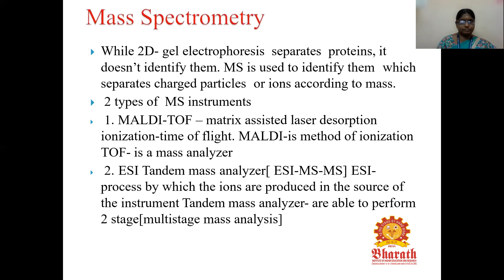There are two types of mass spectrometry instruments. The first one is MALDI-TOF, that is matrix assisted laser desorption ionization time of flight. MALDI is the method for ionization and TOF is the mass analyzer. So here two things are involved. In the first part, we see the method of ionization of the particular ions we have taken, and in the second part, it mainly analyzes the mass of the particular molecule. The second is ESI tandem mass analyzer, ESI-MS, where the ions are produced in the source of the instrument. The tandem mass analyzer can perform a two-stage mass analysis process, so it is named ESI MS/MS.